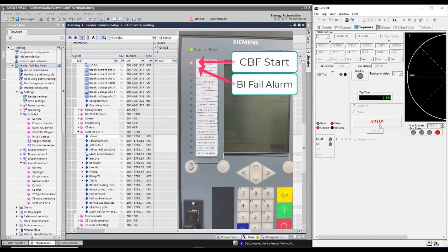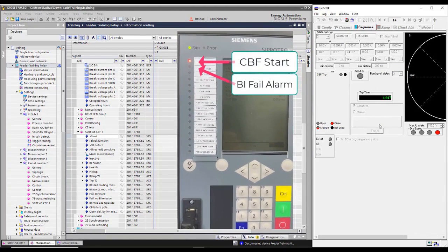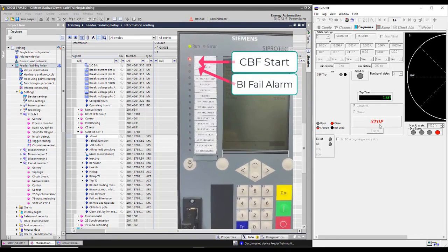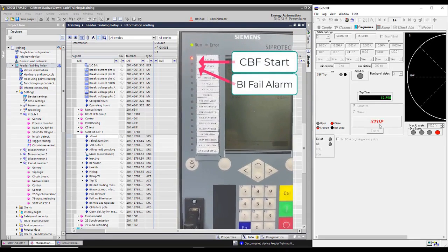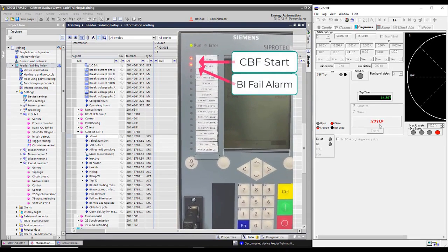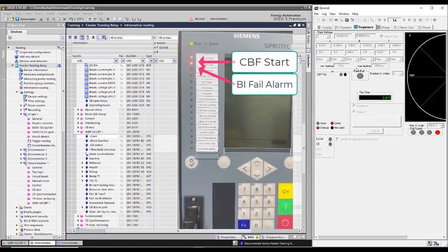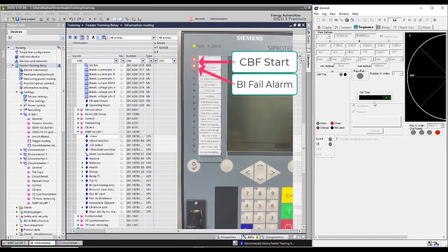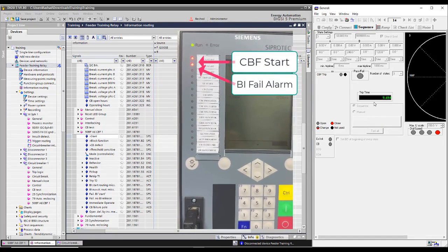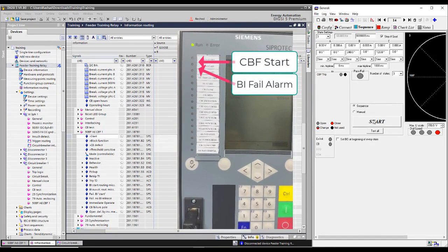During the initiation, it will stay for 15 seconds on the 2nd page, of course 15 seconds with an additional 100 milliseconds, just to make sure the alarm has been triggered. I'll check now. Here on the relay, 1 second left. The alarm has been triggered. It moved to the 3rd page. I'll give it a current, but nothing happened. Why? Because the alarm was triggered, so the relay won't work with you.